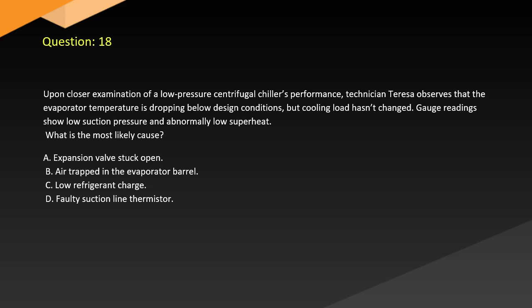Question 18. Upon closer examination of a low-pressure centrifugal chiller's performance, technician Teresa observes that the evaporator temperature is dropping below design conditions, but cooling load hasn't changed. Gauge readings show low suction pressure and abnormally low superheat. What is the most likely cause? A. Expansion valve stuck open. B. Air trapped in the evaporator barrel. C. Low refrigerant charge. D. Faulty suction line thermistor.